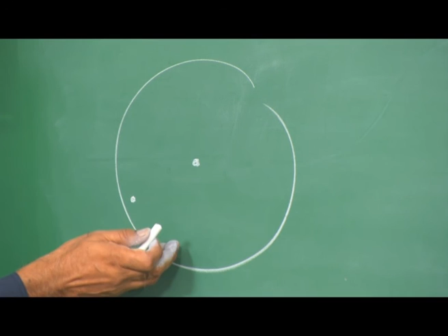In general, if I can ignite the gas at the center, because the length of flame travel is lower, the dP by dt or the violence is going to be larger than if I ignite the gases at the walls. We also find a few things. Depending on the geometry, depending on the blockages, if the flame becomes a detonation in its travel, the dP by dt maximum for a detonation is going to be very much higher, and I cannot use this particular formula because this formula is only true when I have a flame which is propagating. If a detonation propagates, the velocity of propagation is so high that I get a spike or a rapid increase in pressure.